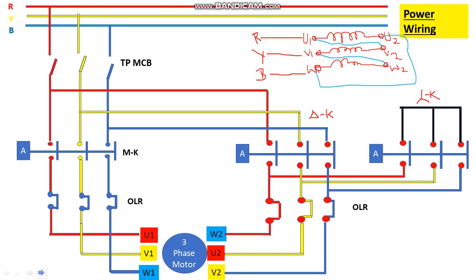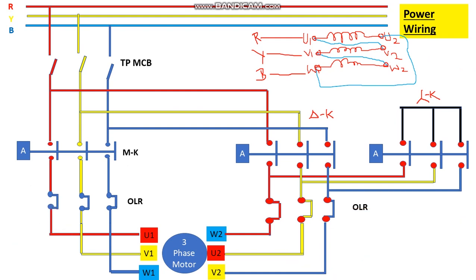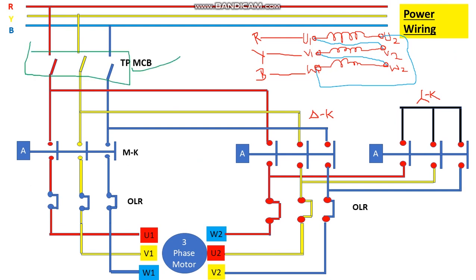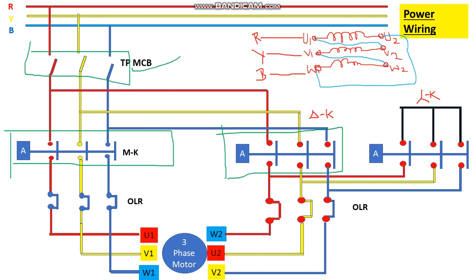Now let's move to the power wiring. This is the single-line diagram — the power drawing of the star delta starter. We have a three-phase bus bar R, Y, B, then a main incomer triple-pole MCB, followed by the main contactor, the delta contactor, and the star contactor.